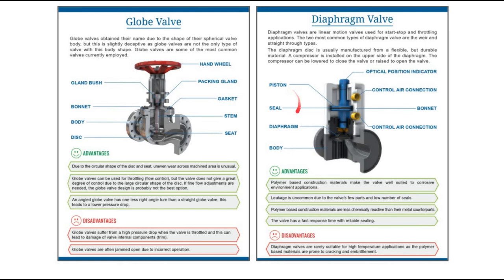Diaphragm valves have several advantages. Polymer-based construction materials make the valve well suited to corrosive environmental applications, and these materials are less chemically reactive than their metal counterparts. Leakage is uncommon due to the valve's few parts and low number of seals. The valve has a fast response time with reliable sealing. Disadvantages: diaphragm valves are rarely suitable for high temperature applications, as the polymer-based materials are prone to cracking and embrittlement at high temperatures. So diaphragm valves are not recommended for high temperature applications.